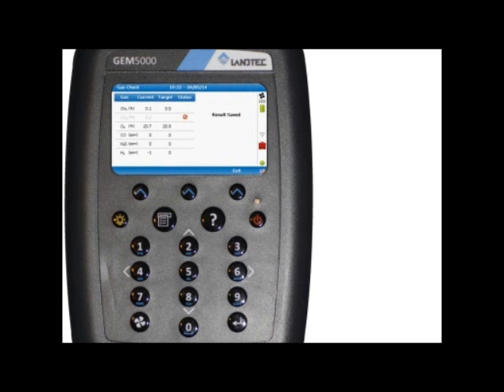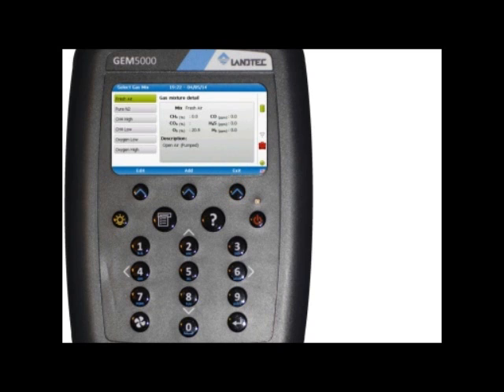Now the results are saved. At this point, you can turn off the gas and disconnect your bottle if you're using the calibration gas bottle. If not, go ahead and press the right soft key again to exit, and this will automatically turn off the pump for you. And that will take you to the select gas mix. And at this point, we're done with step number 1.